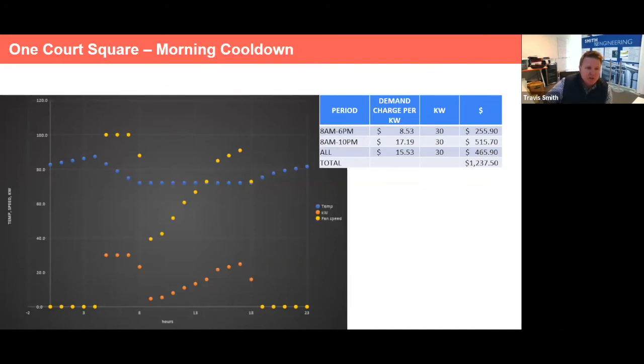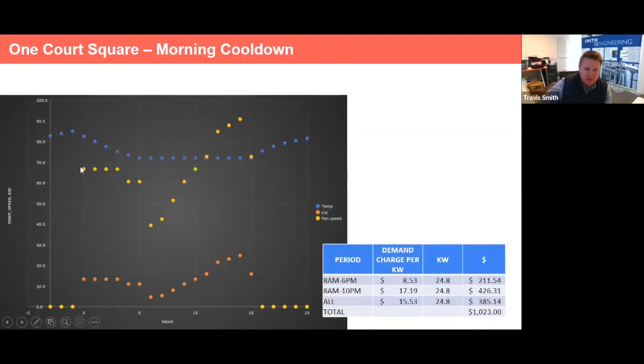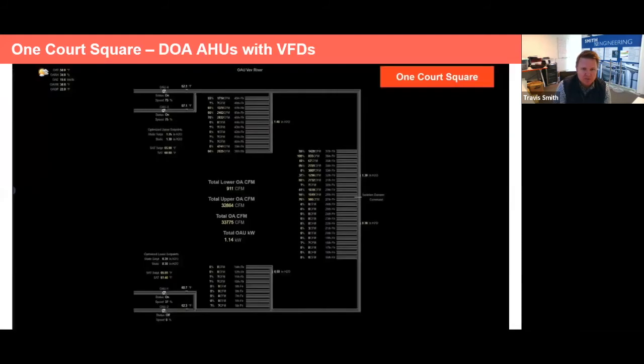This is morning cool down. You can see the traditional optimal start of an air handling unit is really kind of legacy logic left over from when motors were constant speed. So you'd want the optimal start to delay the start as late as possible to reduce the number of hours of a full speed air handling unit fan running. Now that we have VFDs on air handling units, it actually makes a lot more sense for the optimal start to start a little bit earlier so that the VFD runs at a reduced speed to bring it up to the cool down set point. So we use the traditional optimal start logic, kind of trick it a little bit by limiting the fan speed at startup, and that gives us lower kW and lower kWh consumption.